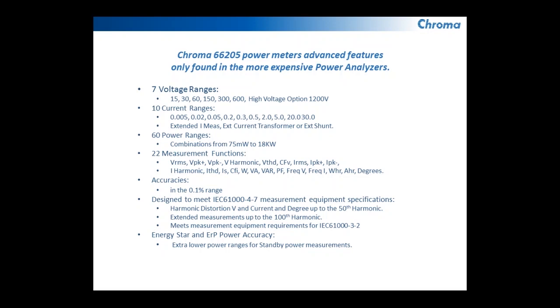This unit has 0.1% accuracy on most ranges, and it's designed to meet the IEC 61000-4-7 standard. This standard is specific for harmonic distortion voltage and current measurements up to the 50th harmonic, and it also includes degrees and actual voltages or percentages. Extended measurements all the way up to 100th harmonic, and measurements are specifically capable of meeting the requirements of IEC 61000-3-2. It also, because of the extended voltage and current ranges, is perfect for measuring Energy Star and ERP, low power ranges, standby power, and efficiencies.